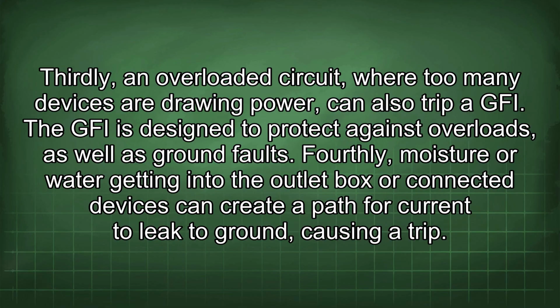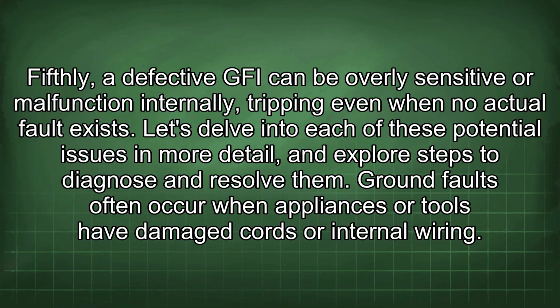Fourthly, moisture or water getting into the outlet box or connected devices can create a path for current to leak to ground, causing a trip. Fifthly, a defective GFI can be overly sensitive or malfunction internally, tripping even when no actual fault exists. Let's delve into each of these potential issues in more detail and explore steps to diagnose and resolve them.